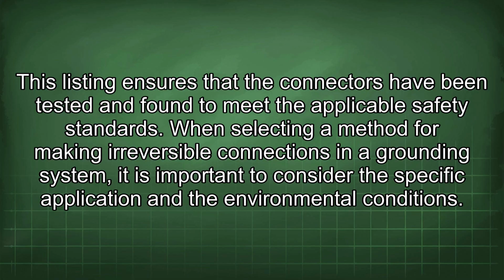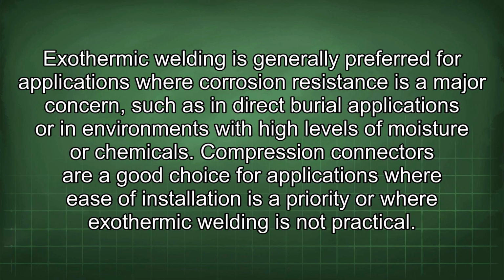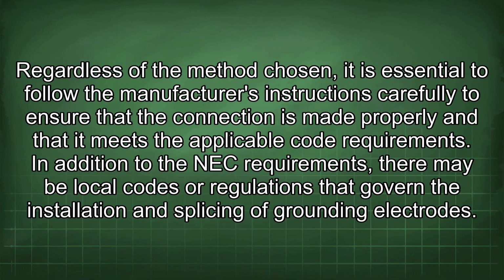When selecting a method for making irreversible connections in a grounding system, it is important to consider the specific application and the environmental conditions. Exothermic welding is generally preferred for applications where corrosion resistance is a major concern, such as in direct burial applications or in environments with high levels of moisture or chemicals. Compression connectors are a good choice for applications where ease of installation is a priority or where exothermic welding is not practical. Regardless of the method chosen, it is essential to follow the manufacturer's instructions carefully to ensure that the connection is made properly and that it meets the applicable code requirements.